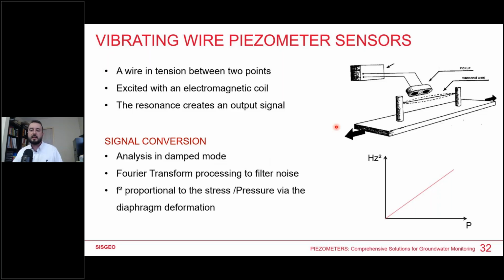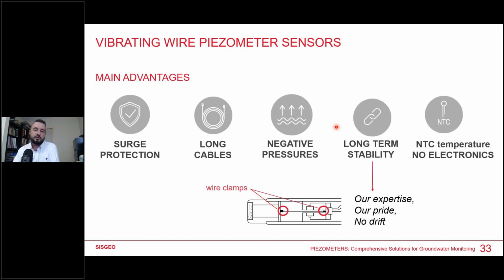What is proportional to the pressure is not the frequency, but the frequency squared. So this is why when you get a sensor, you don't have the measurement directly in frequency. Basically, in the calibration sheets, you will see we express it in digits. Digits are basically squared frequency. The main advantages of this technology are: first, there is an embedded surge protection. Second, it can run very, very long cables. We can measure negative pressure with it because the wire can be more stretched or less stretched, so we can deduce some negative pressure from it. Also, you have an NTC temperature sensor. Anytime you have a vibrating wire sensor in Sisgeo, you also have an associated temperature sensor.